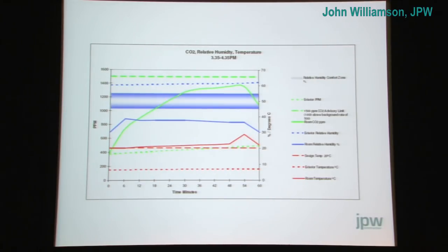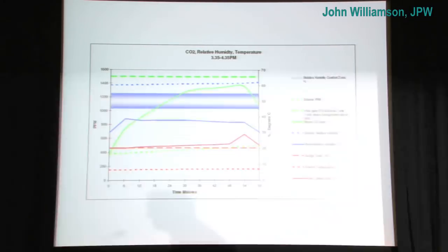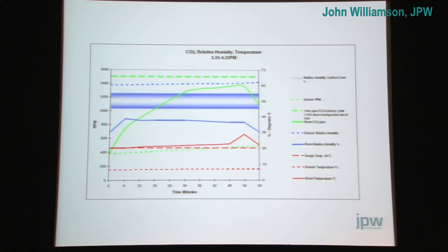However, people walking into the building say, to be honest, it's a little bit dry in here. Yeah, but by all studies, since they've been made, you're in the comfort zone. Interesting. Mid-Wales, outside in their naturally ventilated homes, it's 90% humidity most of the year round. We're near the sea. That's what they're used to living in. So they walk into a building at 50%, in the theoretical comfort zone. We've hit all our targets, but it's perceived as a little bit dry. So these interesting issues started cropping up with people who weren't aware of all the technology.